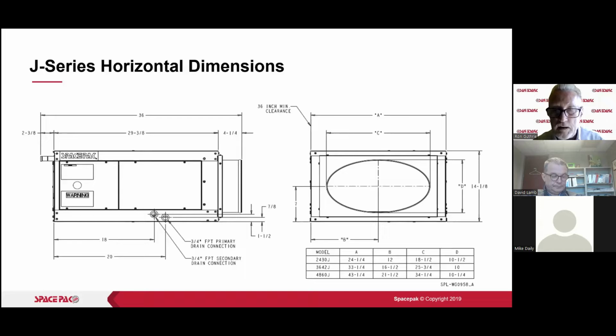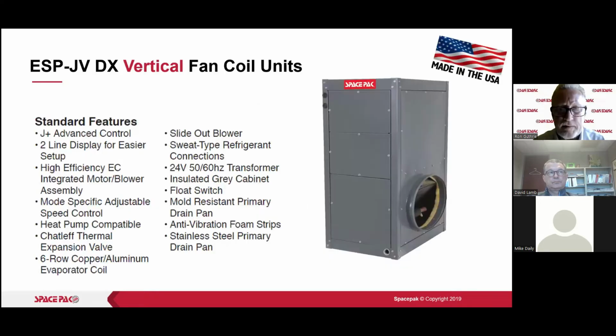It's all designed that way, and then you can push this up into an attic, climb up there, do the install. Last thing you do is climb down and pull that return duct down, connect that to the return air grill, and push that grill up into place and secure it. So that's where that 14 1/8 comes from. That also is related to why we have an oval flange on our unit, because we don't have a lot of height there, but we do want an adequate amount of return air space. So if you were wondering, that's why.